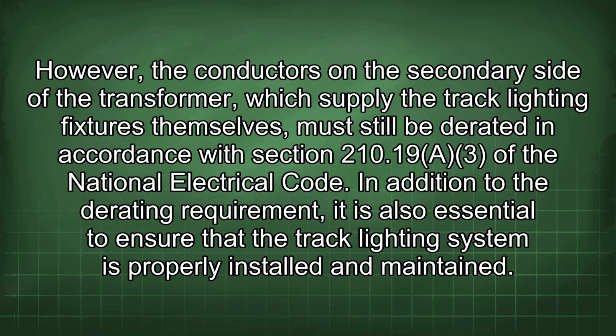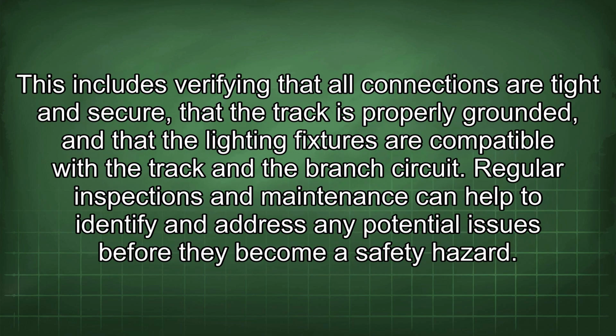In addition to the derating requirement, it is also essential to ensure that the track lighting system is properly installed and maintained. This includes verifying that all connections are tight and secure, that the track is properly grounded, and that the lighting fixtures are compatible with the track and the branch circuit. Regular inspections and maintenance can help to identify and address any potential issues before they become a safety hazard.